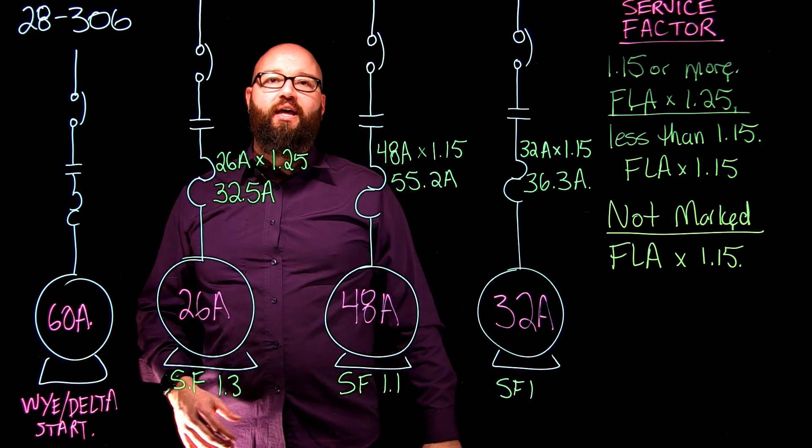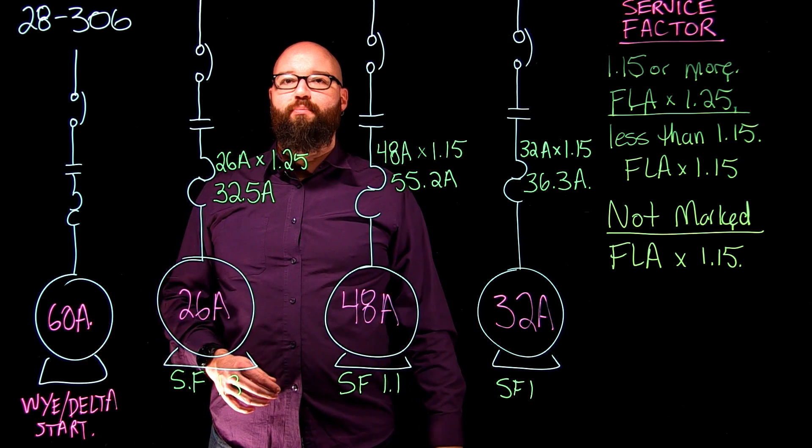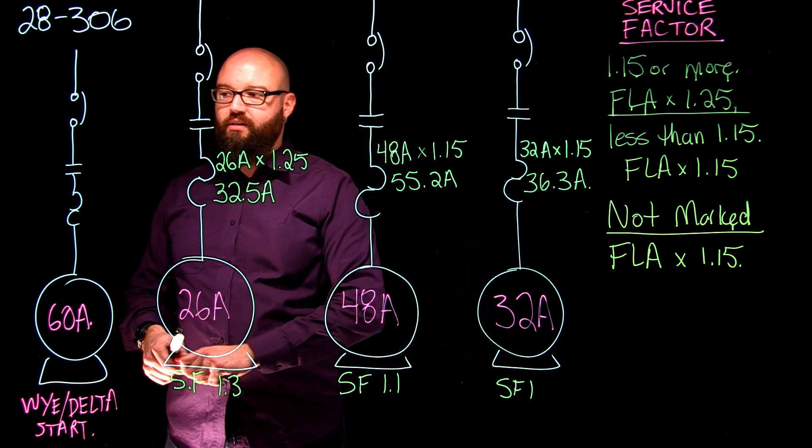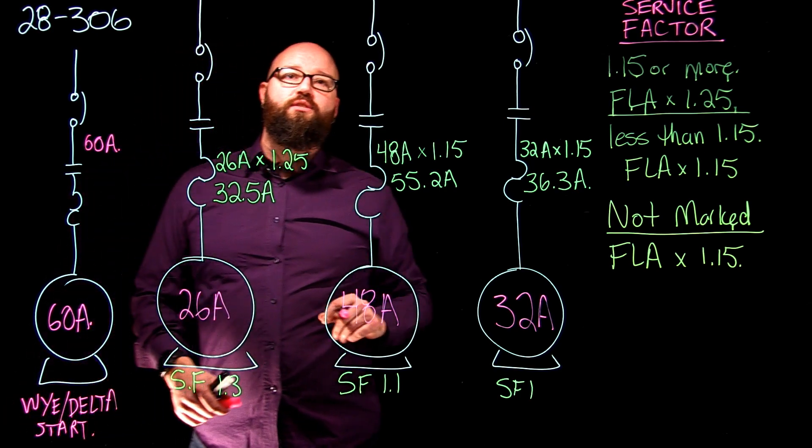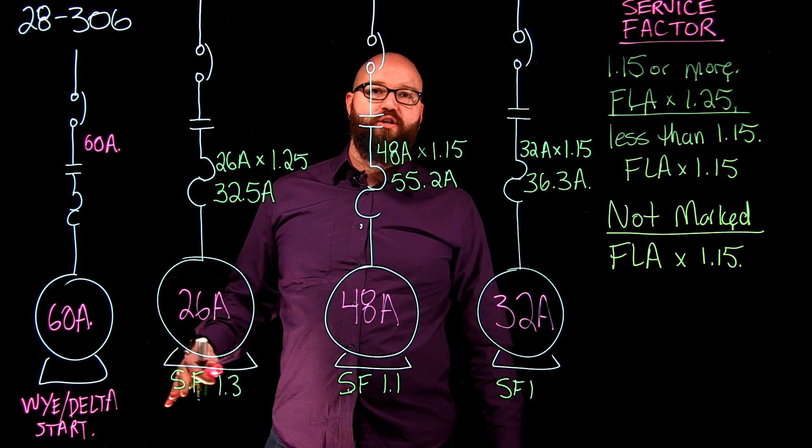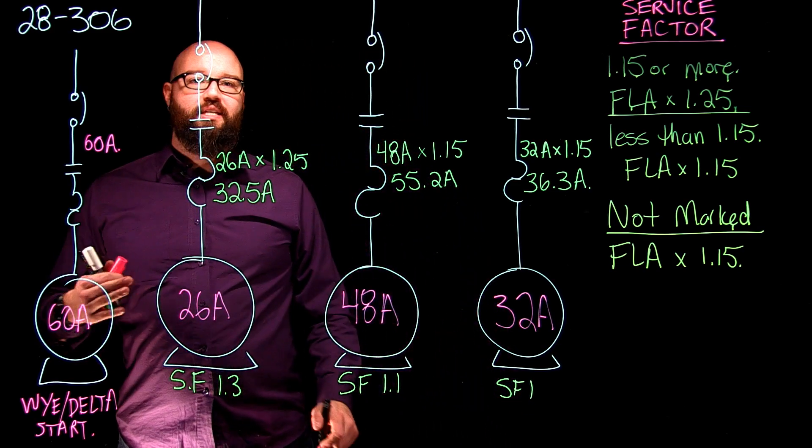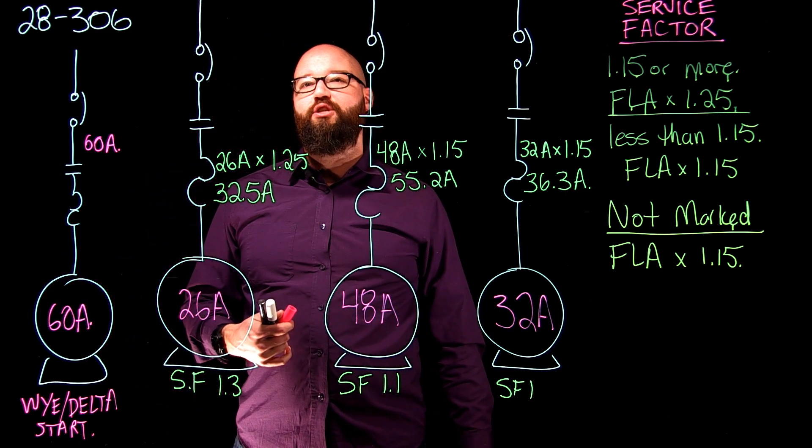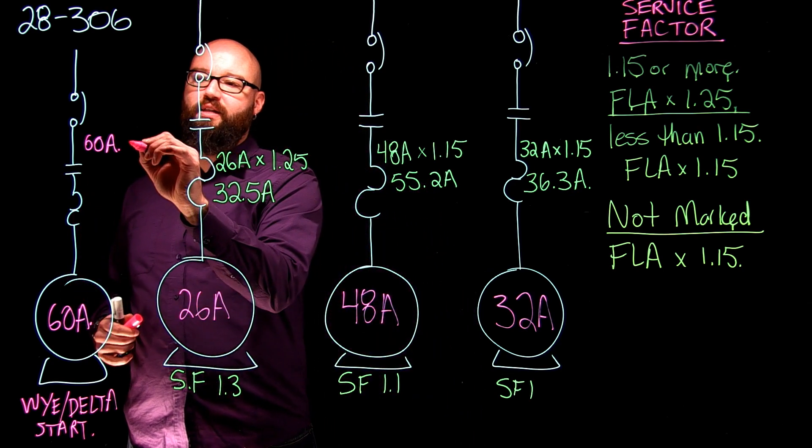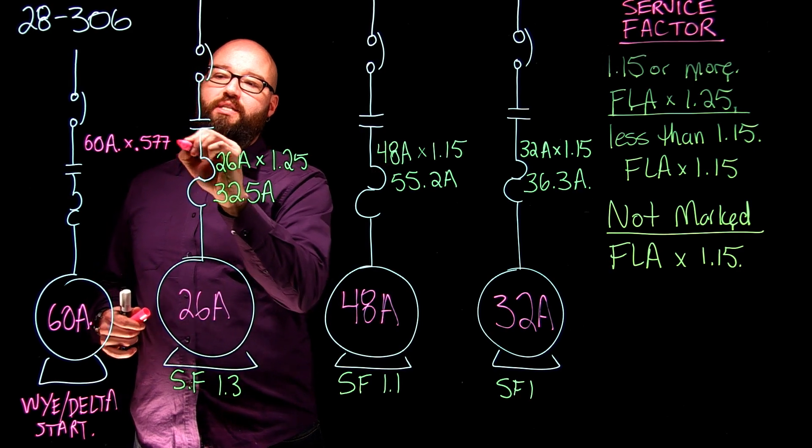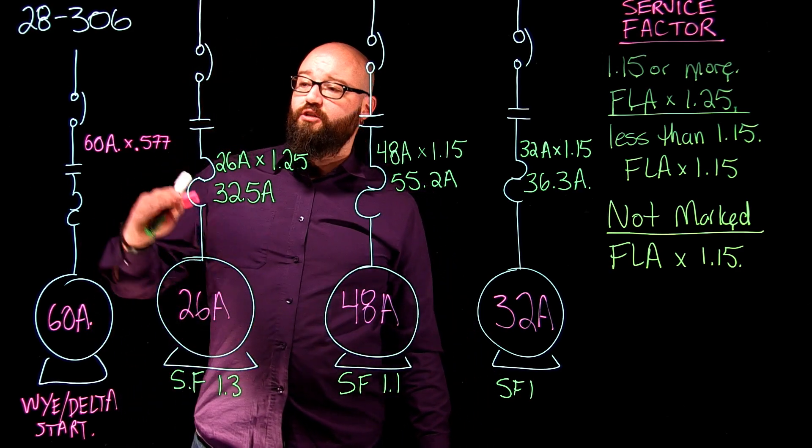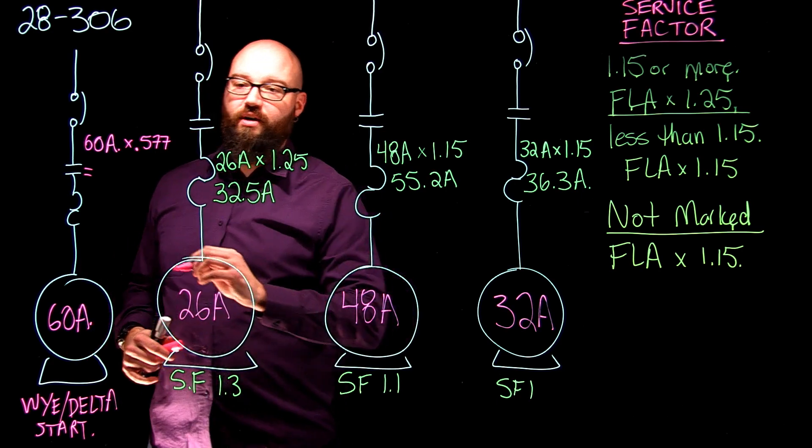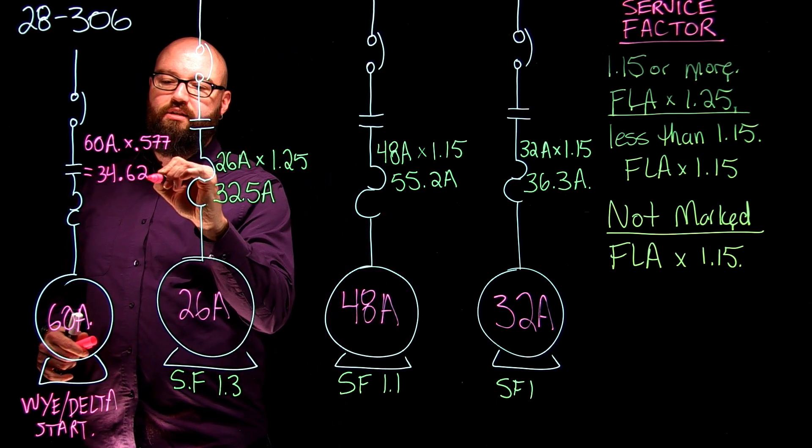When we're given a 60 amp FLA on a Y-delta motor, that 60 amps represents the line current of our delta connection. So we're going to take our 60 amps and what I need to do is find the phase current of my delta configuration because that's where my overloads are. To get that phase current from our delta line current, we know that there is a root 3 relationship there, and we also know that phase current is approximately 57.7% of line current. So we're going to take our 60 amps and multiply it by 0.577, and this is going to give us a delta phase current of 34.62 amps.